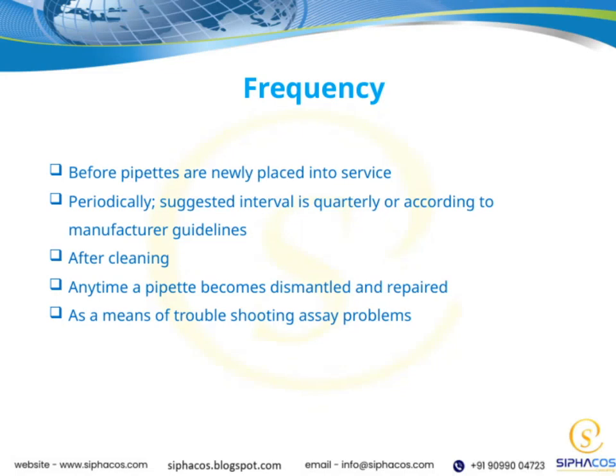Before pipettes are newly placed into service, it's important to ensure they are properly prepared for use. This means conducting a thorough inspection and calibration to guarantee accuracy from the start. Periodically, pipettes should be checked and maintained, typically on a quarterly basis, or according to the manufacturer's guidelines. Following these recommendations helps maintain their precision and reliability over time. After cleaning, pipettes should be re-evaluated to confirm they are still performing correctly.